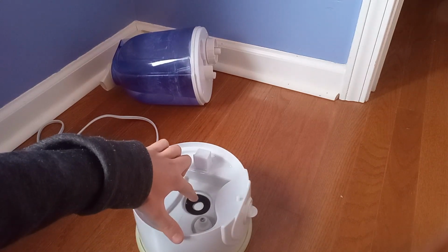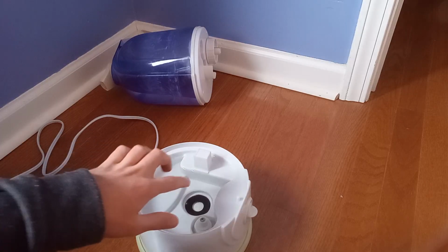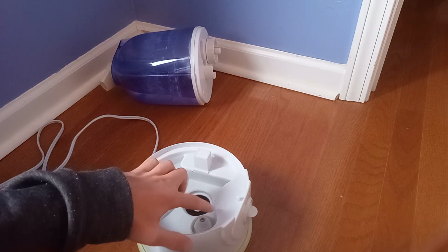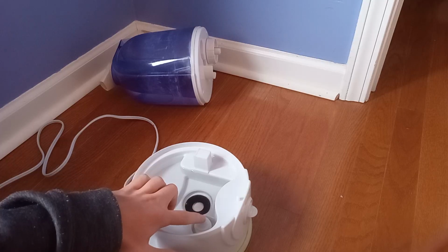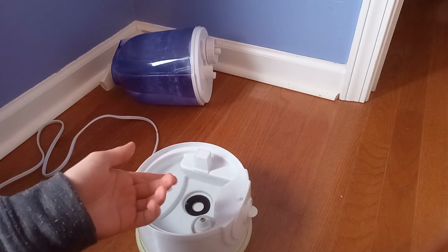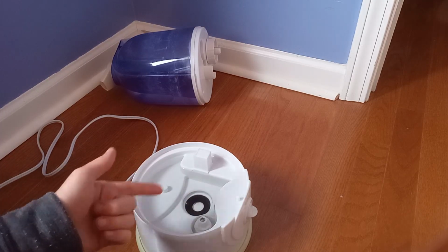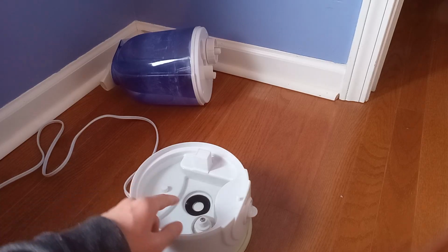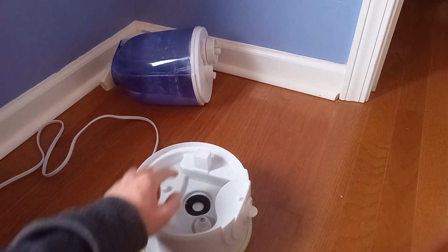This black ring with the white in the middle is the ultrasonic transducer. This little thing right here is a float switch, which prevents the water level from running too low and causing the sensor to run dry, which isn't good.